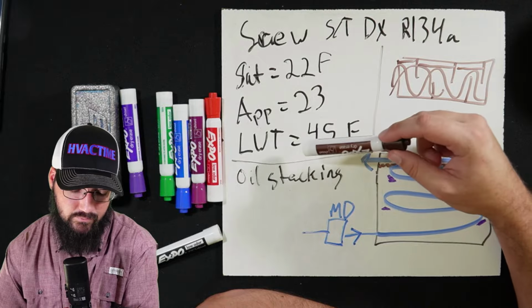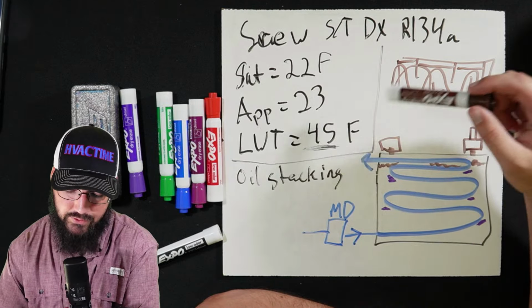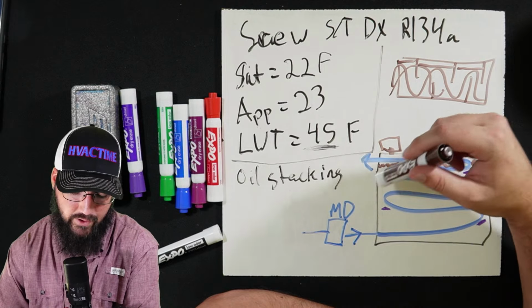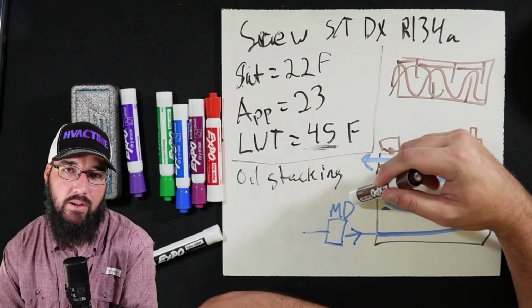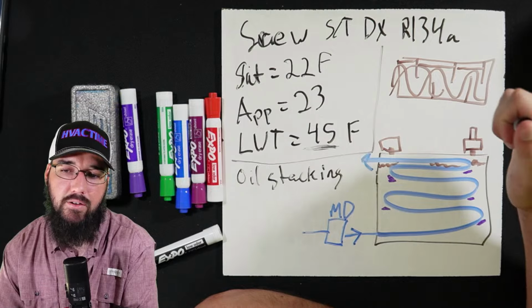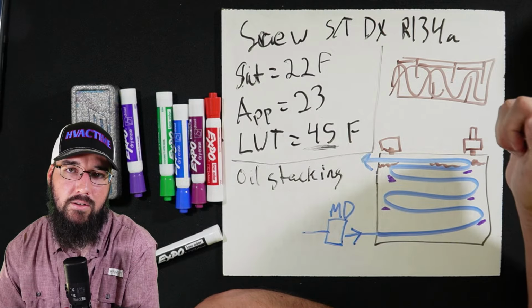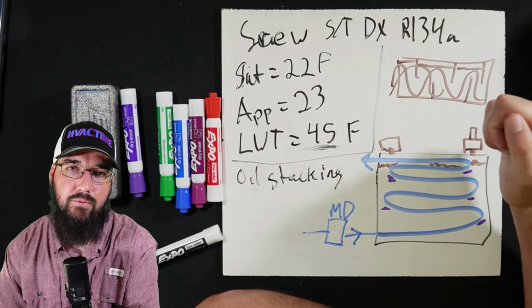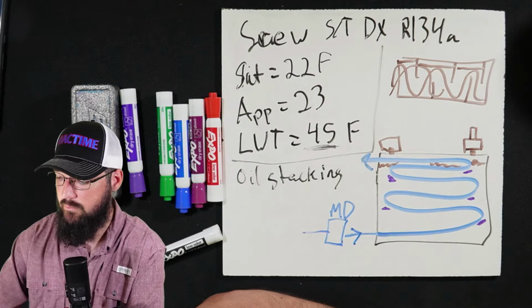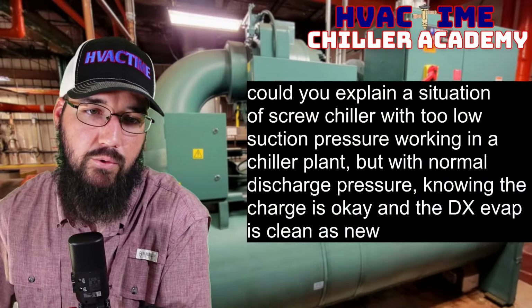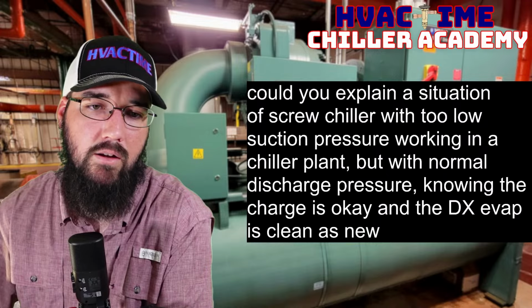So if we're not oil stacking, if it's not air in the evap, then I would look at the metering device. Those would be the three main areas that I would want to be focused on. That's where I would go to troubleshoot this particular problem. So just kind of going back for a quick review.